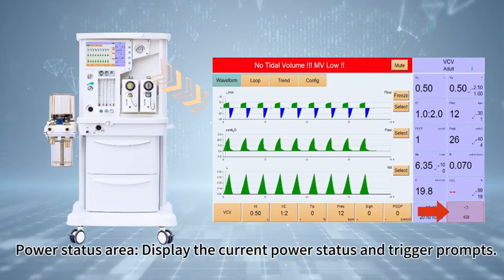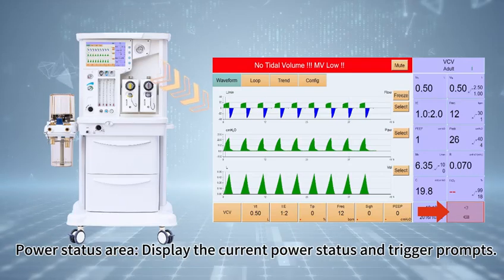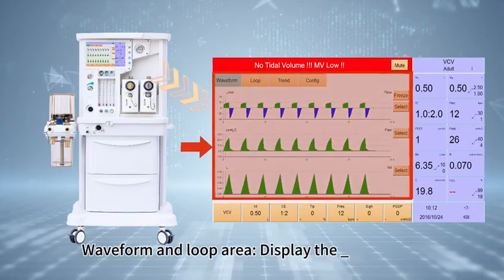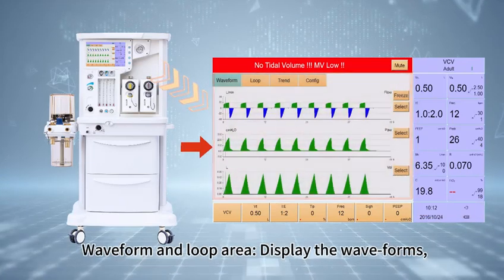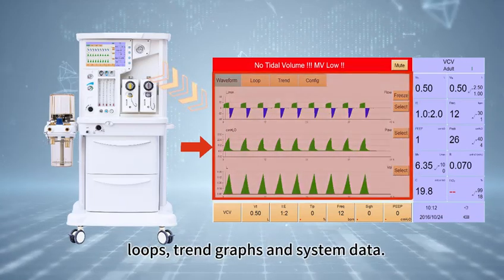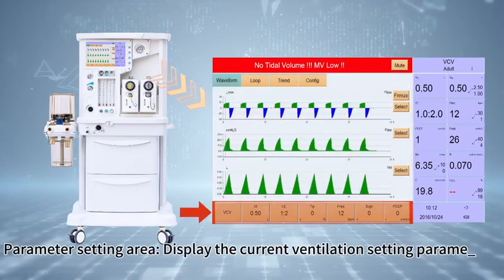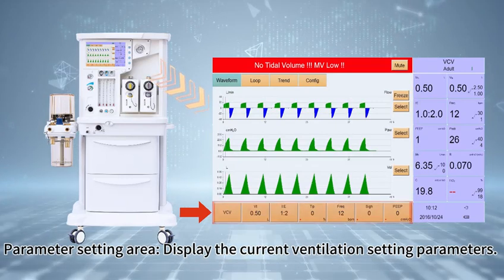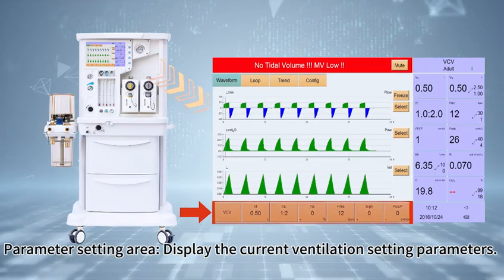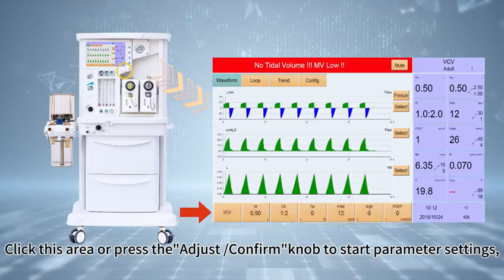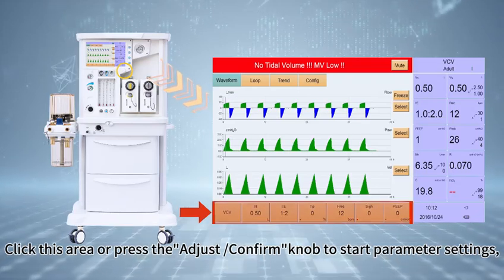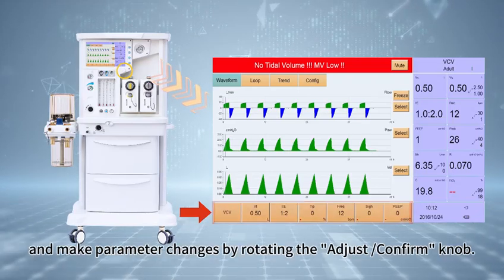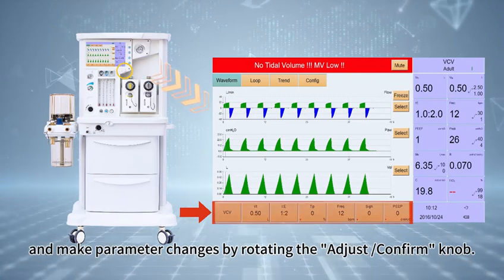Power status area, display the current power status and trigger prompts. Waveform and loop area, display the waveforms, loops, trend graphs and system data. Parameter setting area, display the current ventilation setting parameters. Click this area or press the Adjust or Confirm knob to start parameter settings, and make parameter changes by rotating the Adjust or Confirm knob.